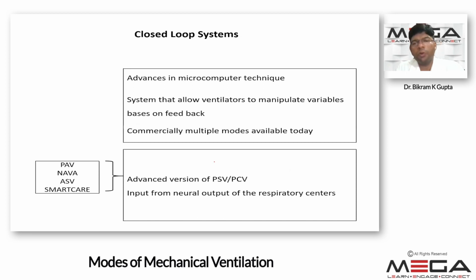Now coming to the next mode, the closed loop system, which now comes with most of the ventilators. And what is this closed loop system? It is based on a microcomputer system that allows the ventilator to manipulate variables based on feedback. The initial generation of ventilators was also based on feedback, but mainly on a single variable. With this type of closed loop system, the ventilator will change its parameters according to different variables. So it is based on different feedback mechanisms, and multiple modes are commercially available today.